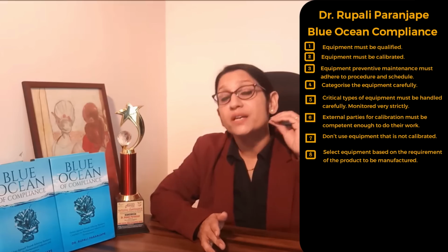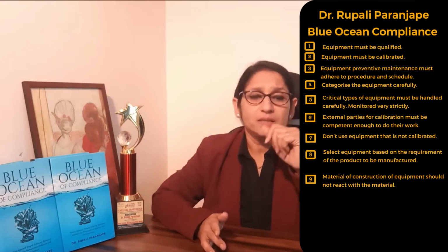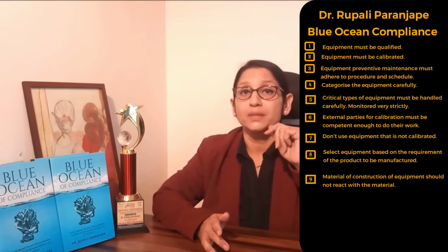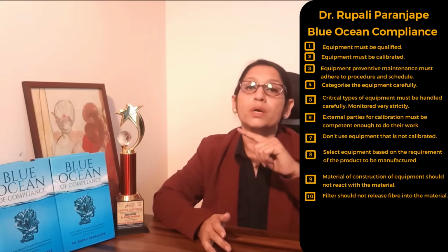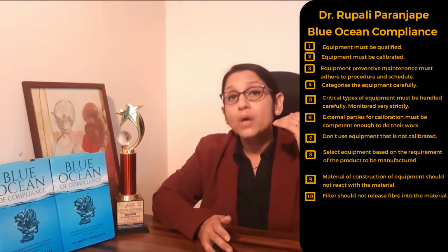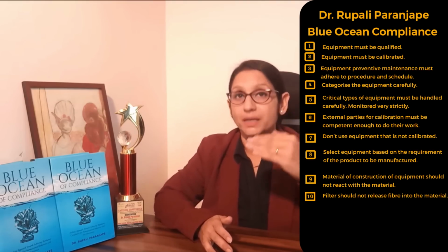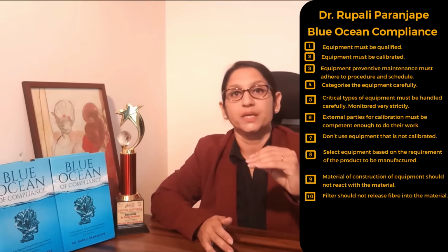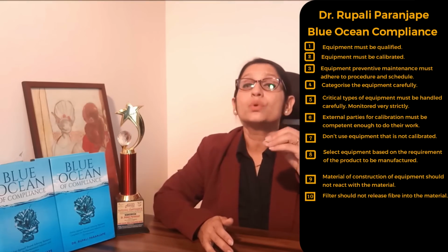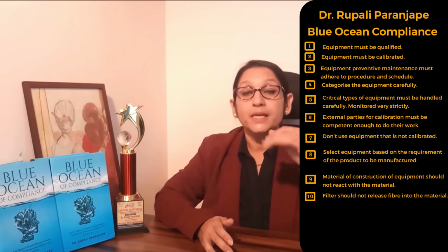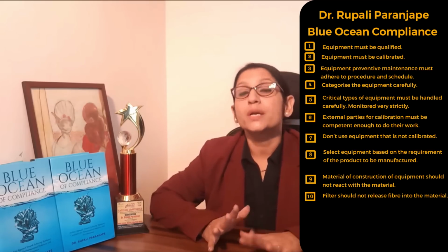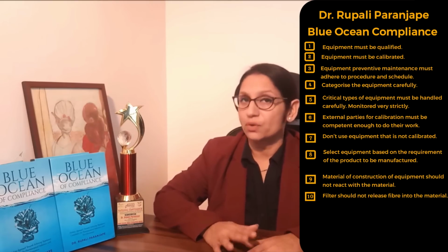After that you will have to ensure that critical equipments are monitored very strictly, right? It also happens that the calibration of many equipments is performed by external agencies or external parties. So you have to ensure that these external parties are competent enough to ensure that the equipment is properly calibrated, and periodically you will have to qualify these vendors that they are able to perform their services properly, so that it will have a very good impact on the working of your equipment, right?